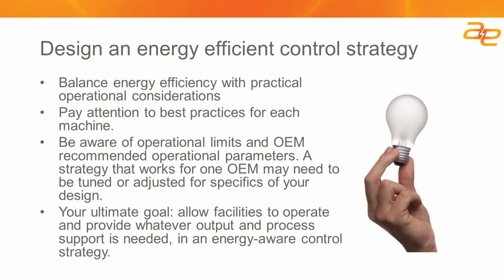In conclusion, one of the things I do want to state is that equipment sequencing in theory is simple. The idea is that we try to run as many machines at their optimal levels to address the specifics of the process or the facility in terms of its utility needs, while minimizing the number of machines that need to run, such that we only run one machine at a partial load condition.